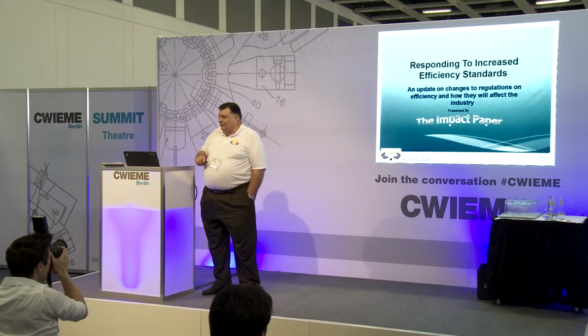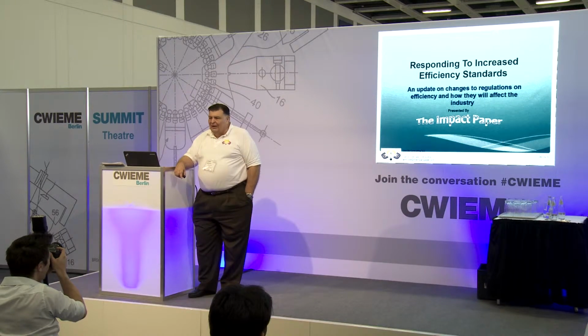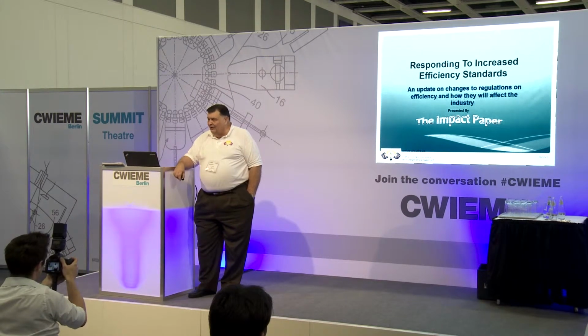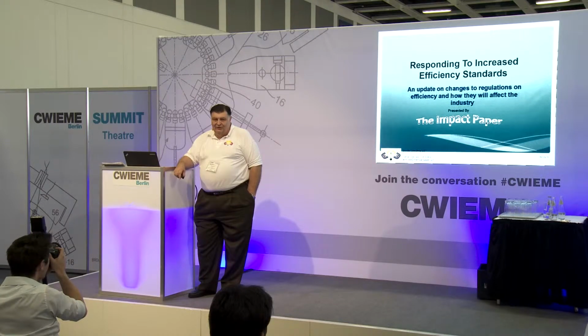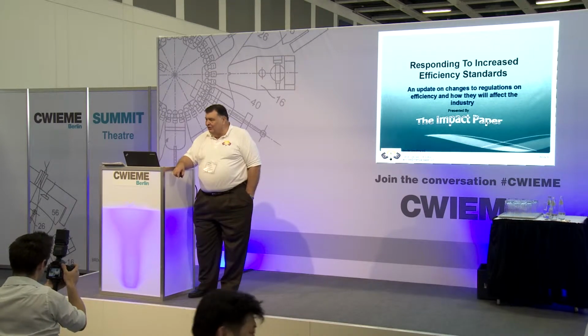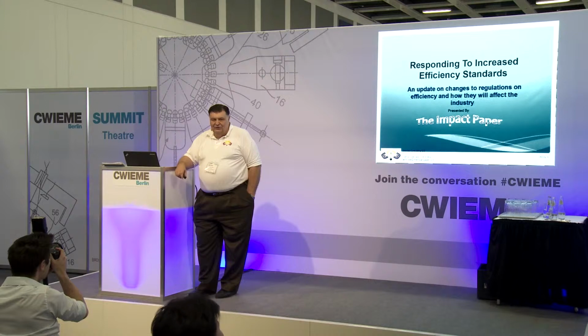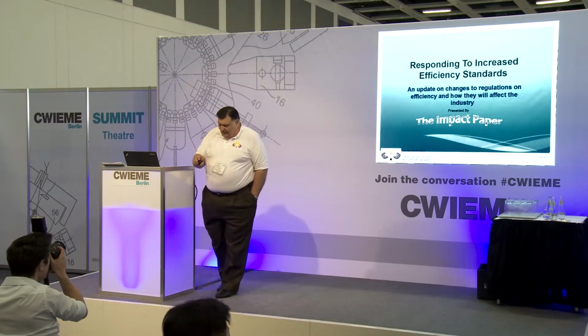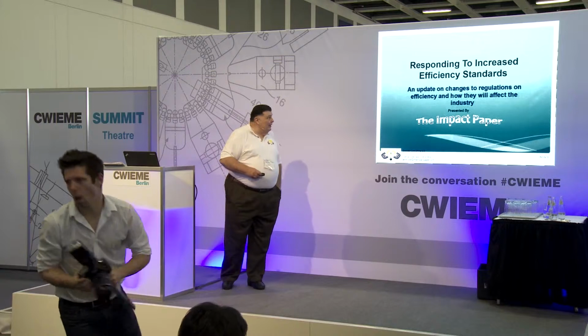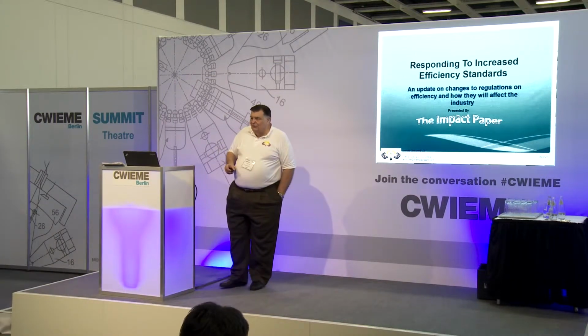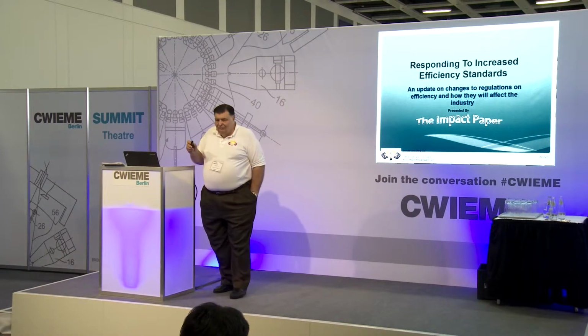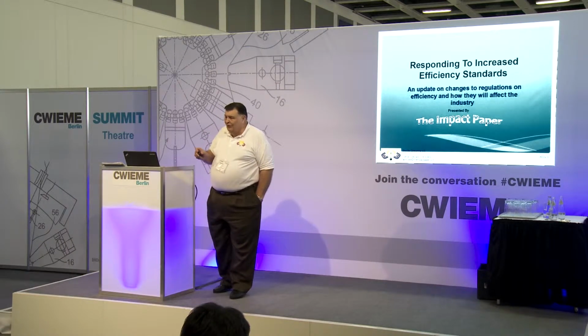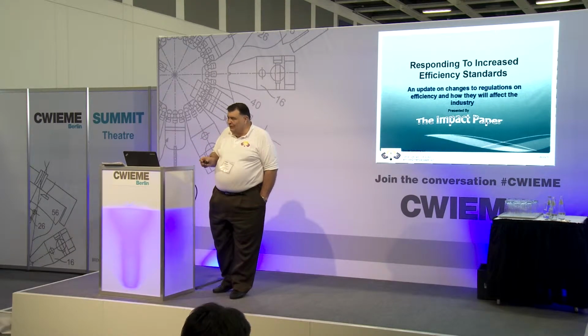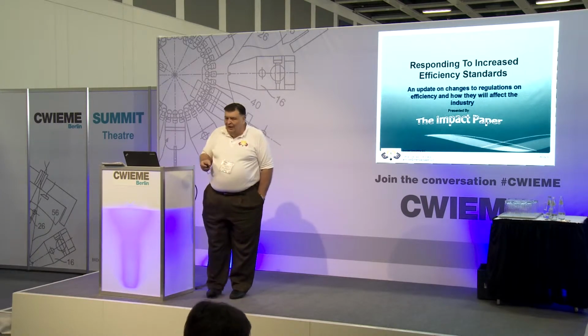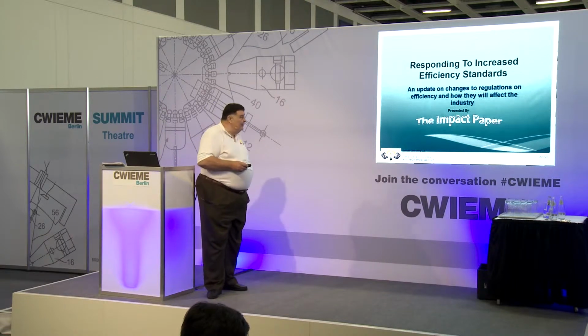Let me give you a little background. For the last 10 years I've been deeply involved with the distribution transformer industry in the United States as a director of strategic sourcing for one of the major distribution transformer manufacturers. So what we want to talk about is all the new efficiency standards that are coming out, and we're going to concentrate primarily on distribution transformers, both liquid immersed and dry type, and what their impacts are going to be on the materials that go into them.